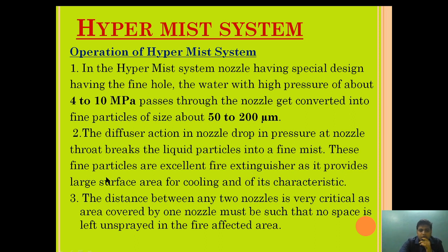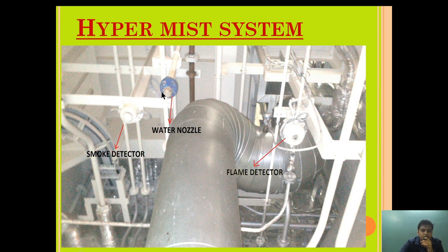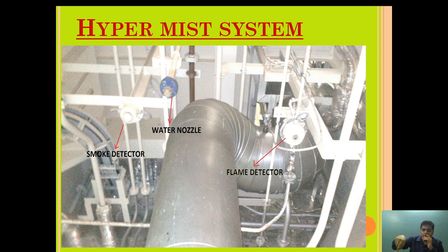These fine particles are excellent fire extinguishers as they provide a large surface area for cooling. The fog-like mist causes both a smothering and a cooling effect. The distance between nozzles is very critical — the area covered by one nozzle must be such that no space is left unsprayed in the fire-affected area. For example, if one nozzle covers 5 meters but the boiler platform is 10 meters, two Hypermist nozzles must be provided to cover the whole area.